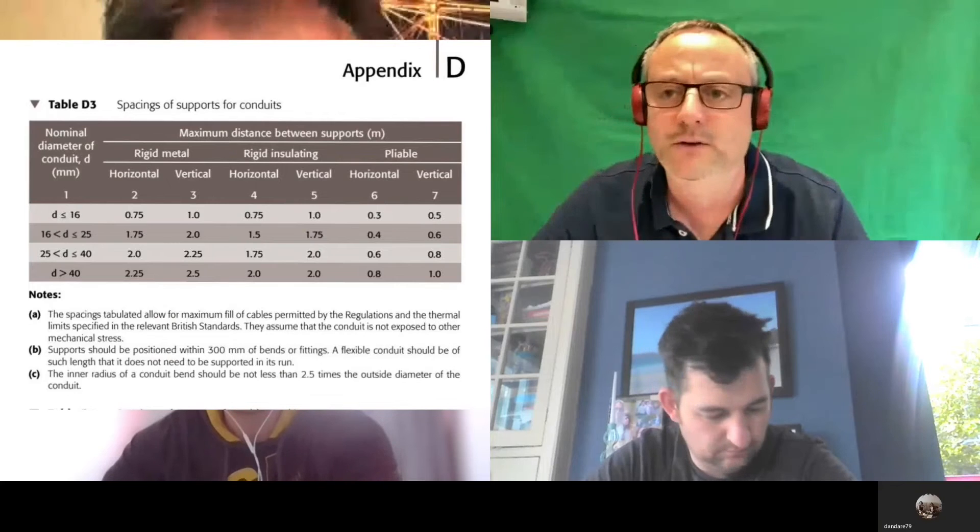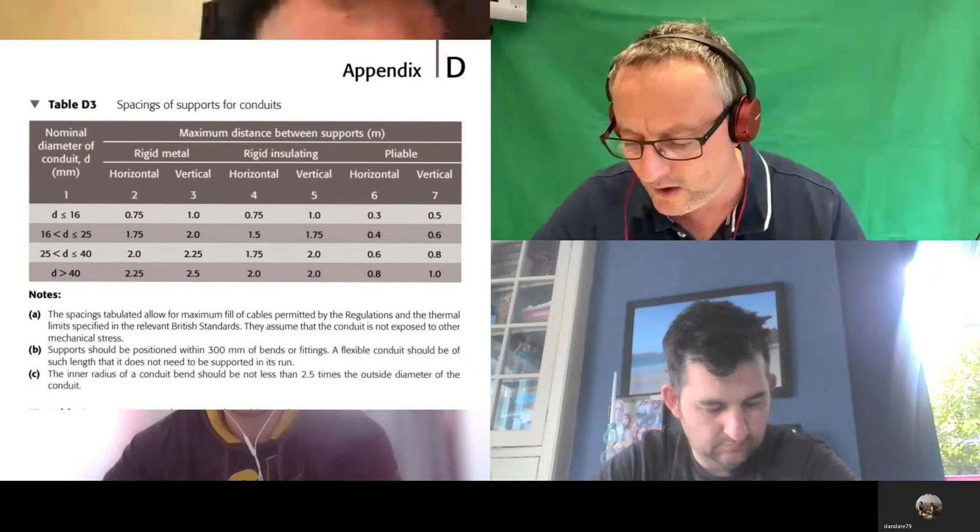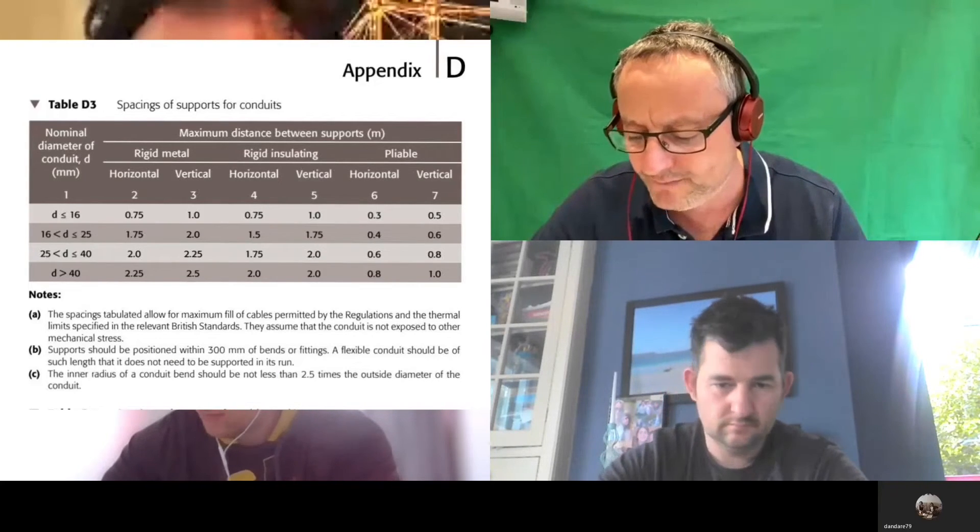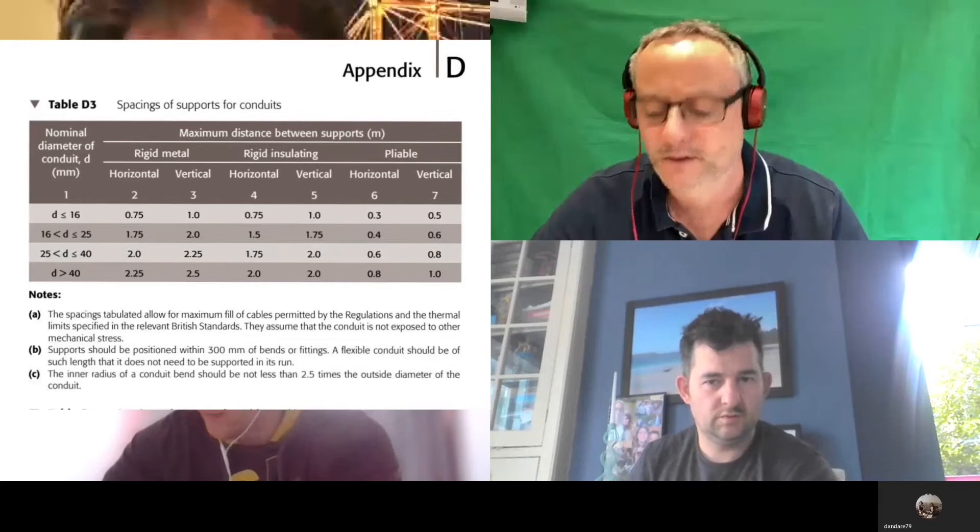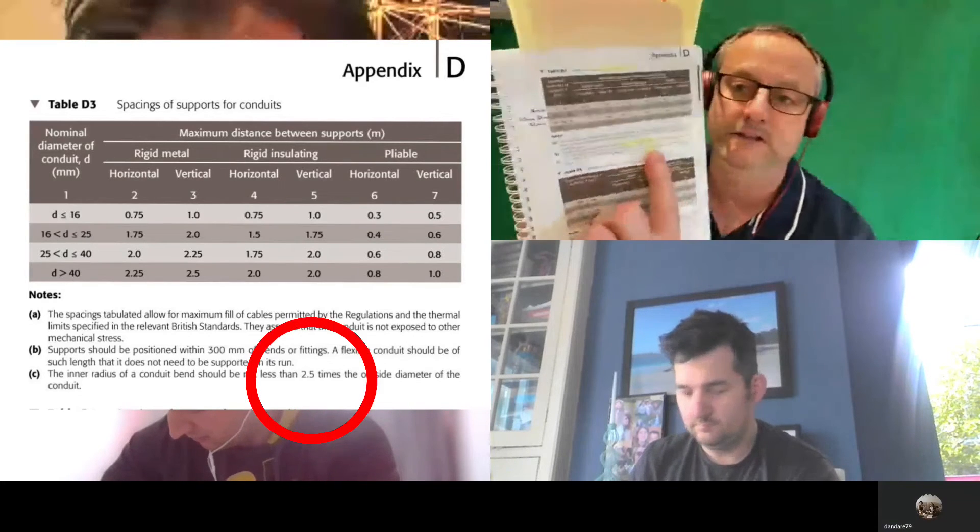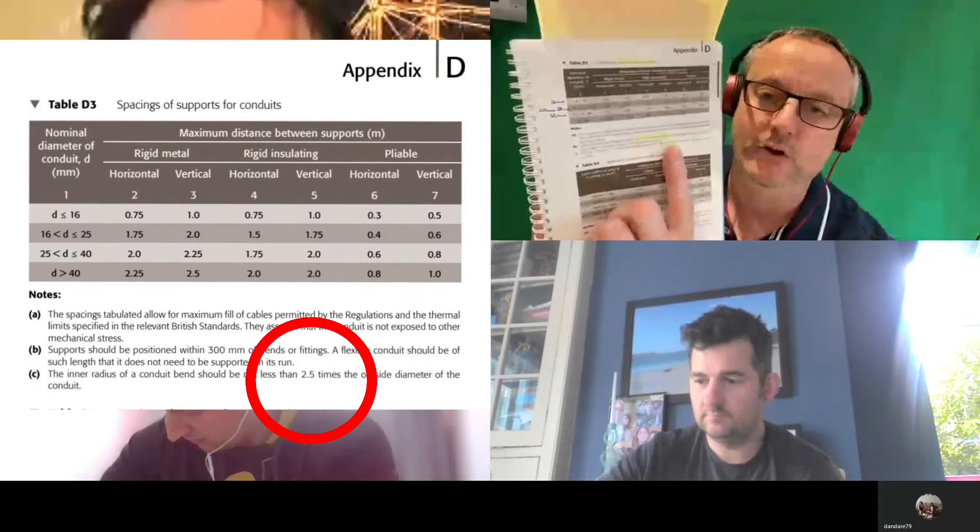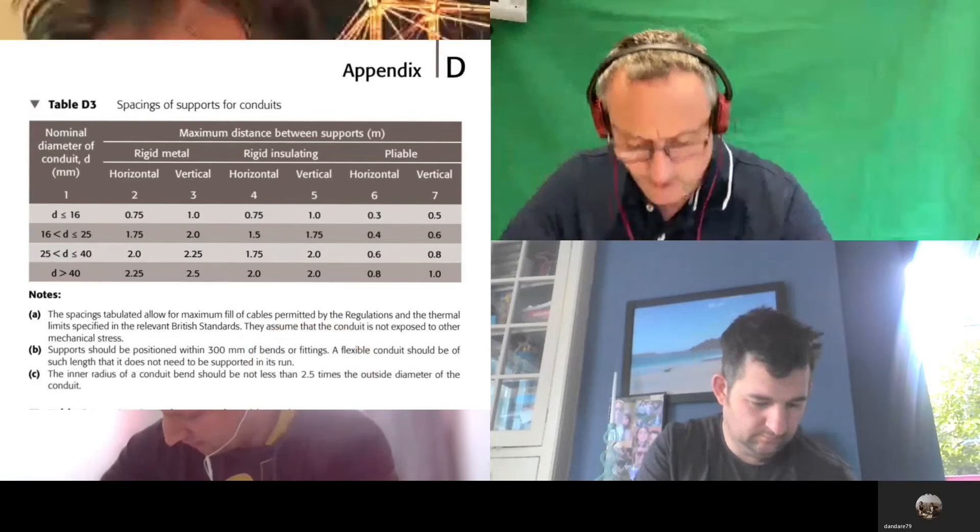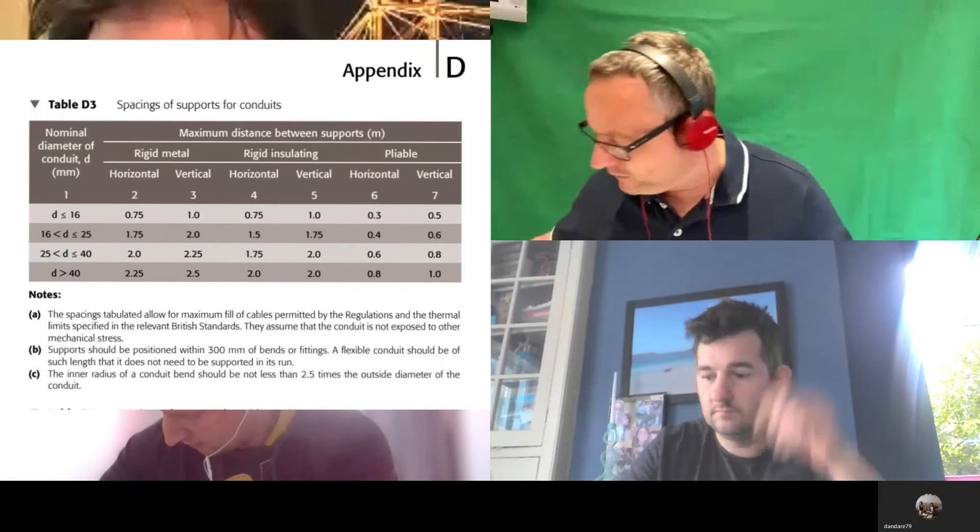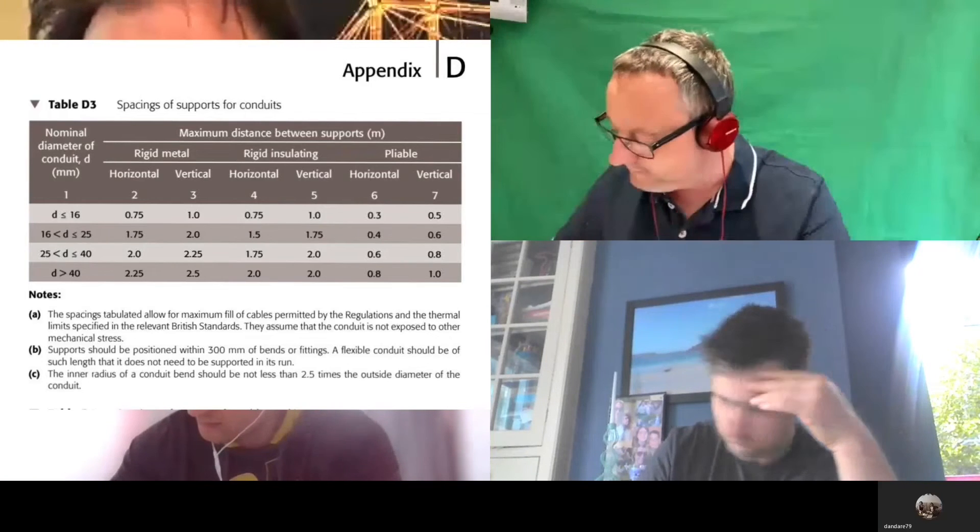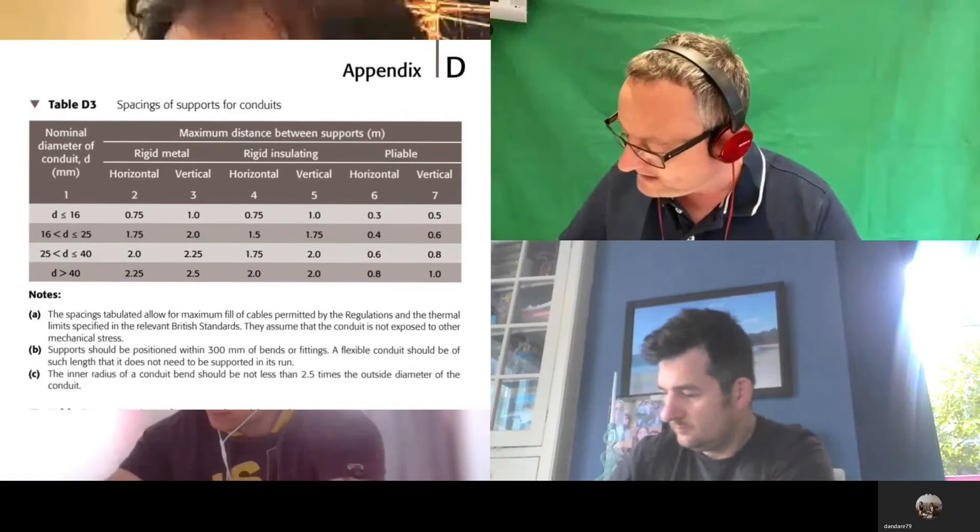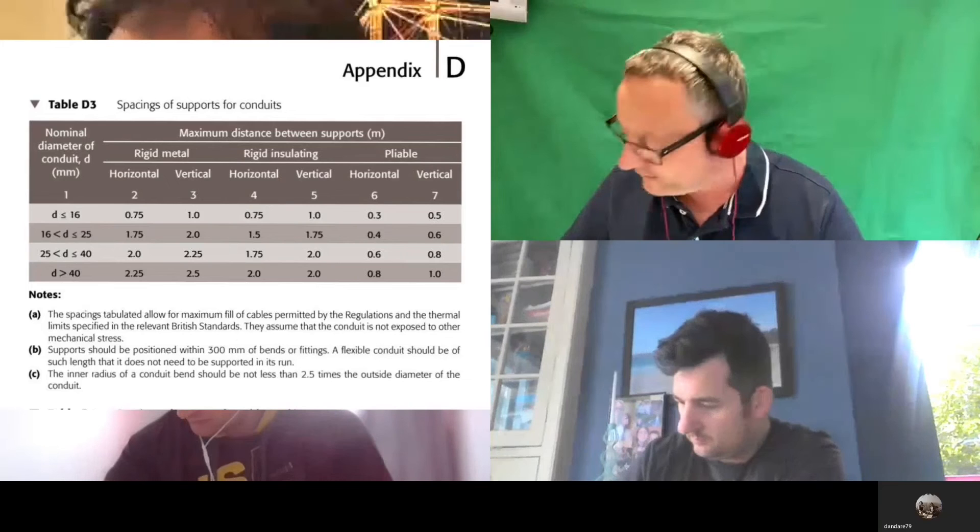I've highlighted that if you haven't done it already. And in Note C, it goes back to what Ed said to me earlier on: what was the factor for the diameter? Two and a half times diameter. I don't make this stuff up because it's in the on-site guide. Highlight that as well. What I want you to do now is on your page nine, put the horizontal and vertical spacings for the maximum distance for these supports if it was metal conduit. I want 16, 20, 25, and 32 horizontally and vertically for metal conduit please.